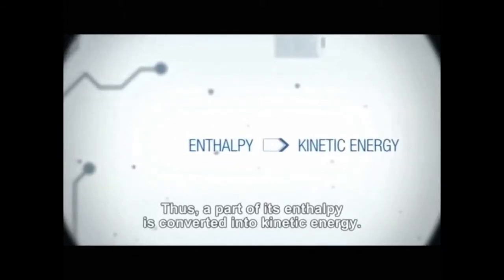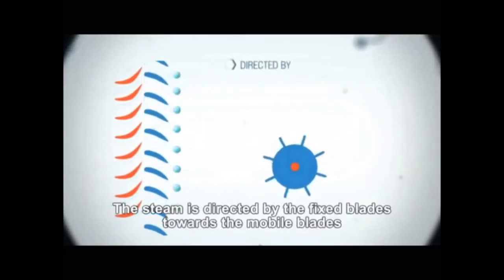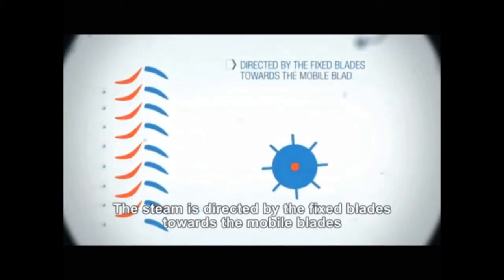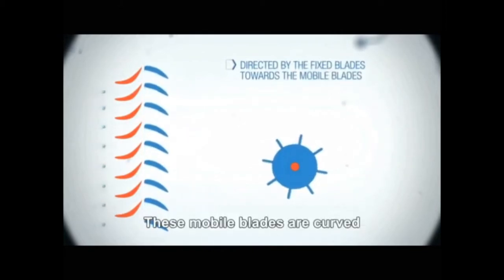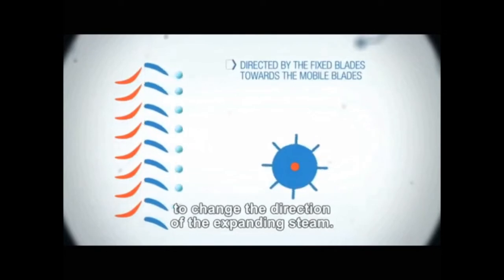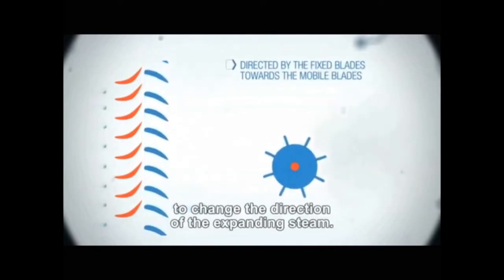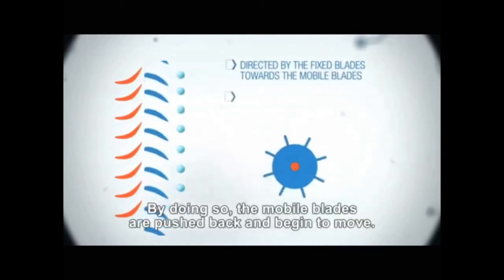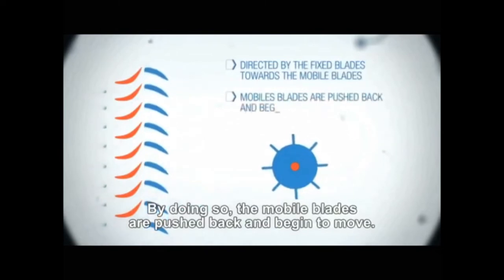Thus, a part of its enthalpy is converted into kinetic energy. The steam is directed by the fixed blade toward the mobile blade, which it flows across. These mobile blades are curved to change the direction of the expanding steam. By doing so, the mobile blades are pushed back and begin to move.